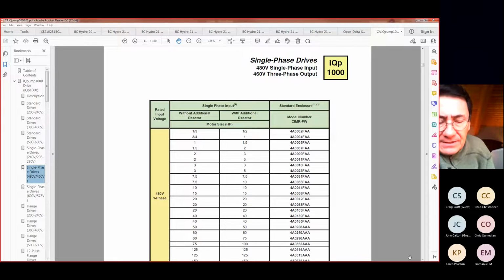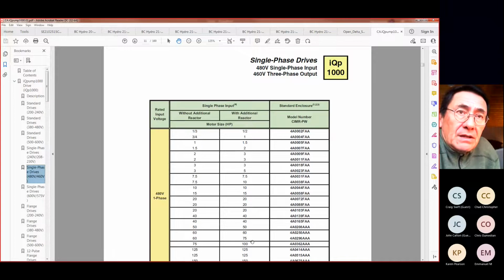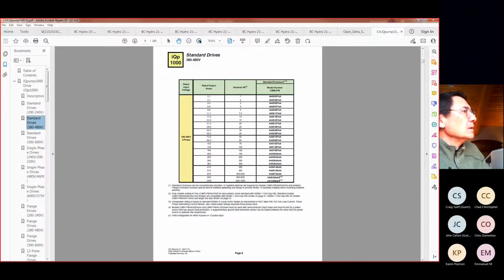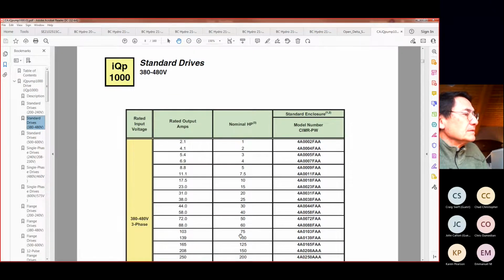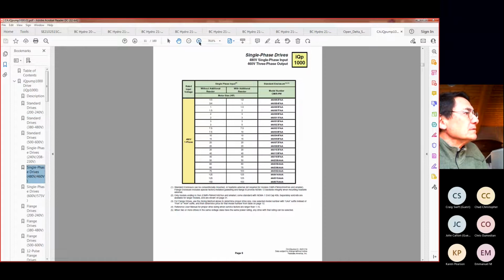The issue is we want more capacitance. And because, as you can see, sizing up 1 doesn't get you more capacitance. So in the case of a 40 going to a 50, you're not helping the situation. And in the case of a true single phase load, going from 40 up to 60 or 75 and getting the next class of capacitance isn't going to be enough in many cases. What happened is UL came out and said, okay, we are going to have a separate rating for VFDs based on the power supply. And when it's three-phase power supply, we can use these ratings. But when it's single phase, again, 75 horse, 103 amp. When it's a single phase application, these are the UL approved ratings for the Yaskawa product.